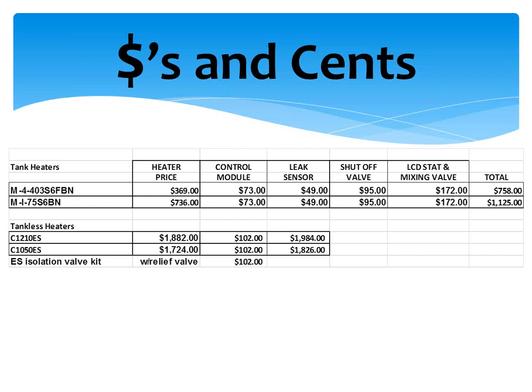One of the other things, as Ryan was saying, is if sediment builds up on the bottom of the tank - remember my joke about heating a bucket of water on the other side of a brick wall - that sediment means we're firing underneath that tank for a longer period to get the temperature up. We get more expansion and contraction on the bottom shell of that tank, and we've got that glass lining in there. So over time, firing through all that sediment loosens things at the welds in the bottom of the tank, and that's where we start cracking the ceramic coating, letting water into the tank and killing it.